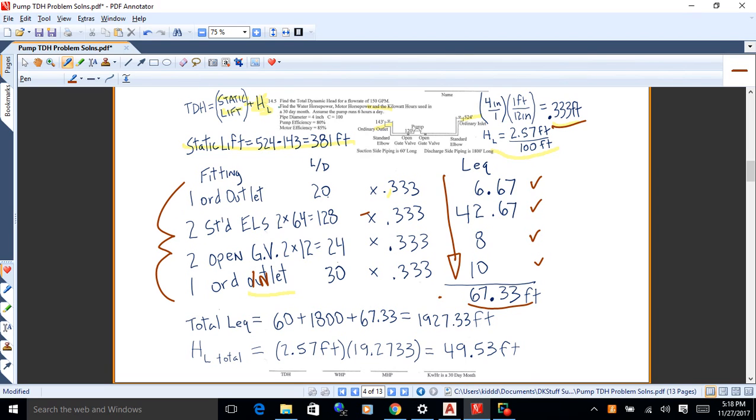We've also got 60 feet of pipe on the left of the pump, and 1800 feet of pipe to the right. So we just add everything up. 60, 1800, 67.33, we get 1927.33 feet. The head loss is 2.57 feet per hundred. We got that for the four inch pipe C100 and 150 gallons per minute. Multiply that by the number of hundred foot lengths of equivalent lengths of pipe, 19.27, you get 49.53 feet. So that's the total head loss in the system.